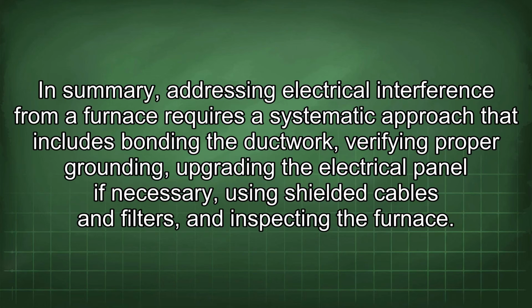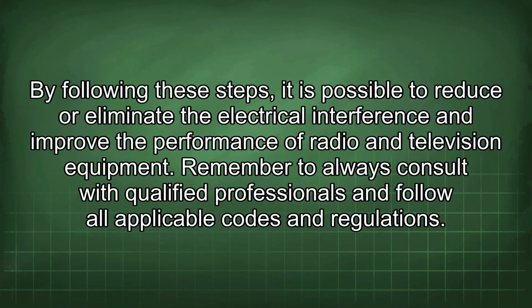In summary, addressing electrical interference from a furnace requires a systematic approach that includes bonding the ductwork, verifying proper grounding, upgrading the electrical panel if necessary, using shielded cables and filters, and inspecting the furnace. By following these steps, it is possible to reduce or eliminate the electrical interference and improve the performance of radio and television equipment. Remember to always consult with qualified professionals and follow all applicable codes and regulations.